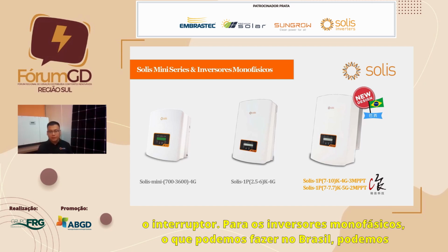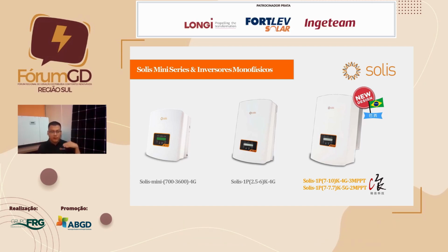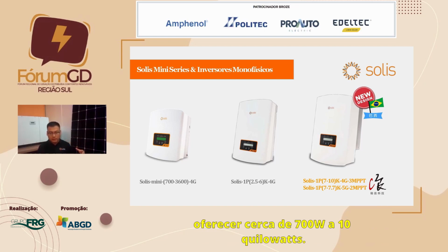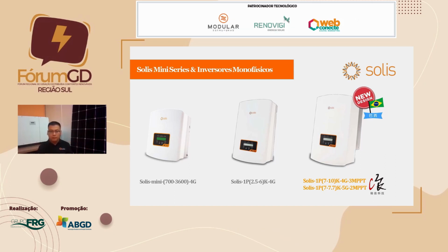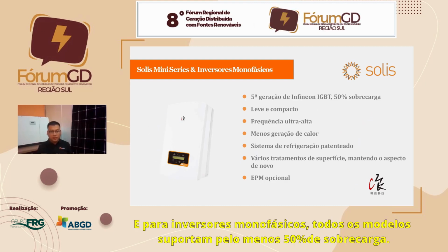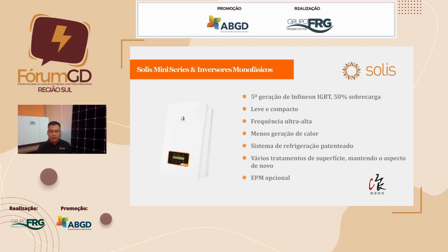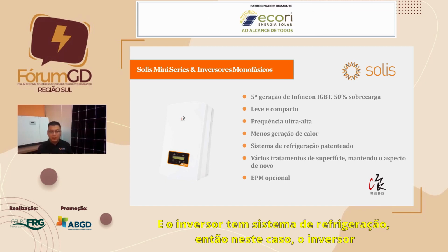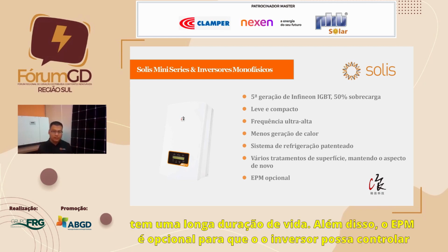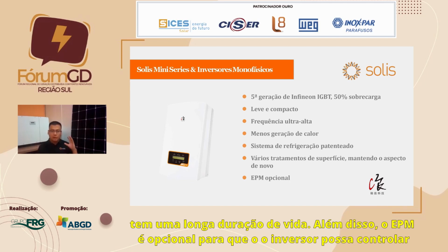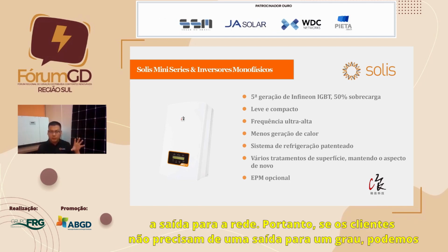For the single phase inverter, now in Brazil we can offer from 700 watt to 10 kilowatt, with 1 MPPT up to 3 MPPT. All single-phase inverter models support at least 50% overload. The inverter has a patented cooling system, so it has a long lifetime. Also, EPM is optional, so the inverter can control the output to the grid. If the clients don't need any output to the grid, we can control the inverter.